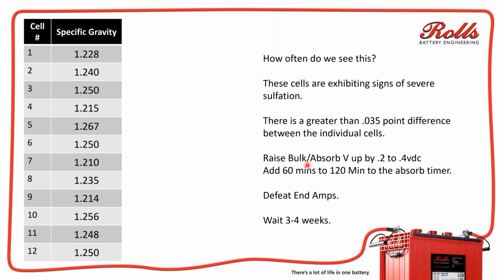But the first thing I wouldn't do is do an equalization. The first thing I would do is adjust your charging voltages. More than likely, what caused this are your charging voltages and or your absorption times, or you have an end amps setting that is programmed on the charge controller or the inverter or whatever charger you're using. There's something wrong with the setting.